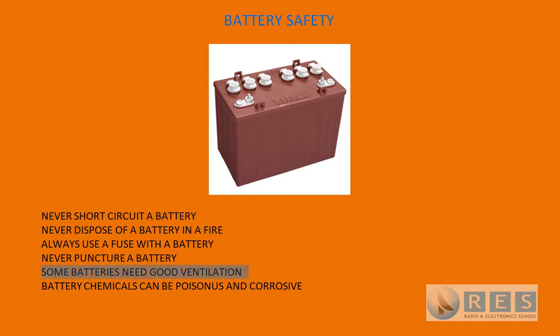Some batteries need good ventilation. Lead acid cells need good ventilation because they produce gases, and those gases are combustible. If you have lead acid cells in a confined box, those gases can build up and explode if ignited. The chemicals in batteries are poisonous and corrosive.